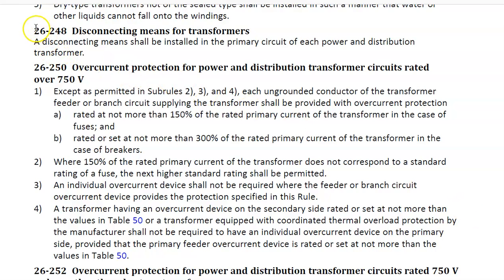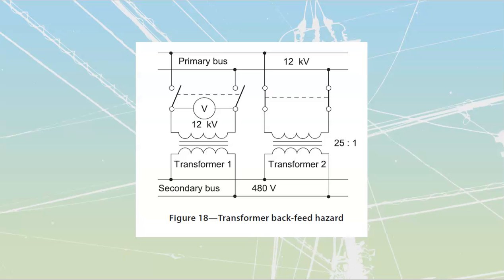Then we have the big one we wanted to get to: disconnecting means. It says that the disconnecting means shall be installed on the primary or infeeding side of each power and distribution transformer. Note that they say power and distribution - they don't say control transformer and they don't say signaling transformer. We don't always need them inside of those, but inside of anything that is power and distribution, we do.